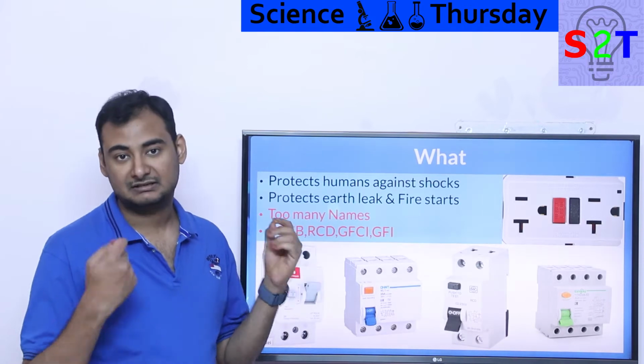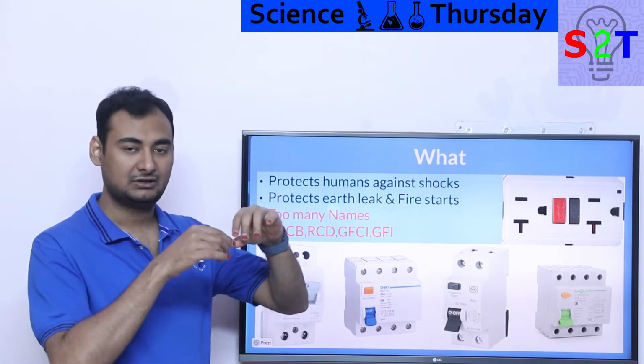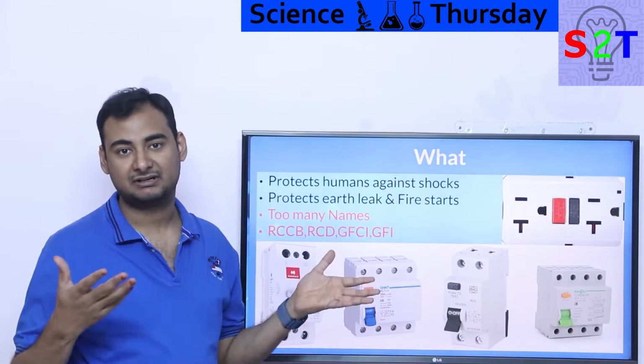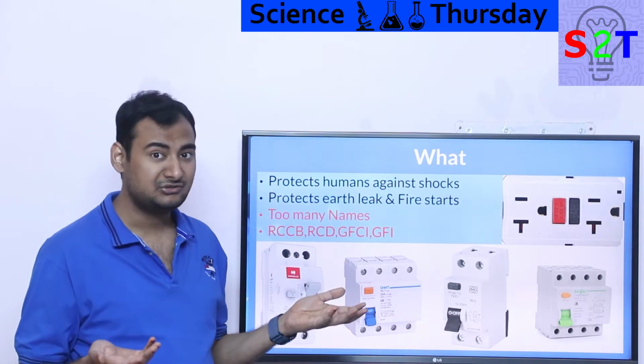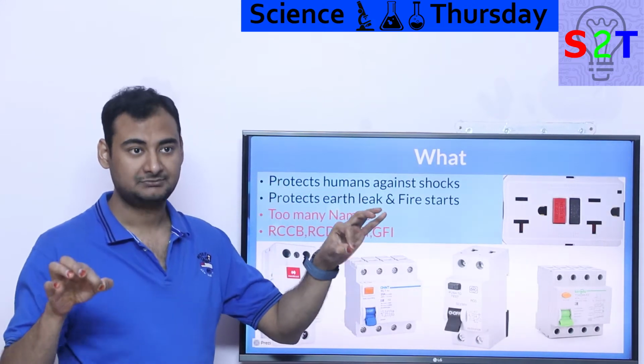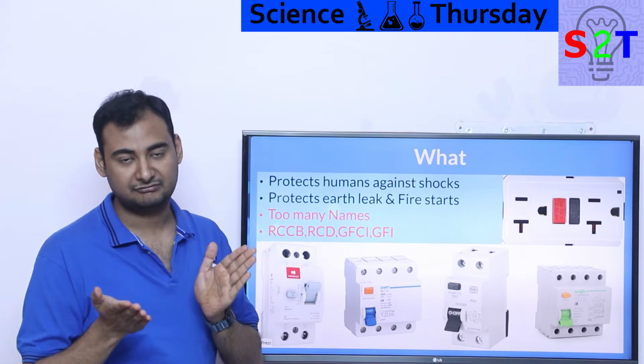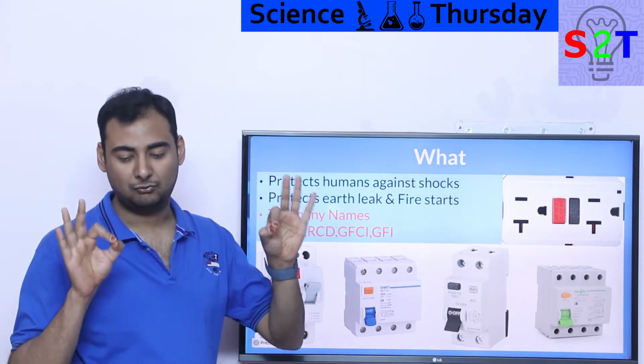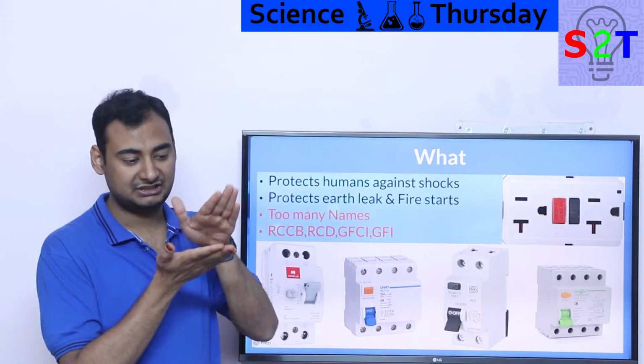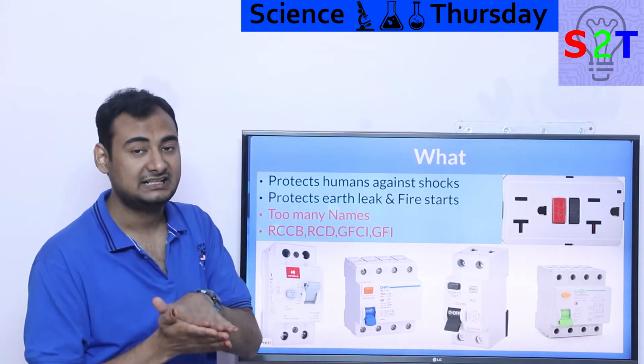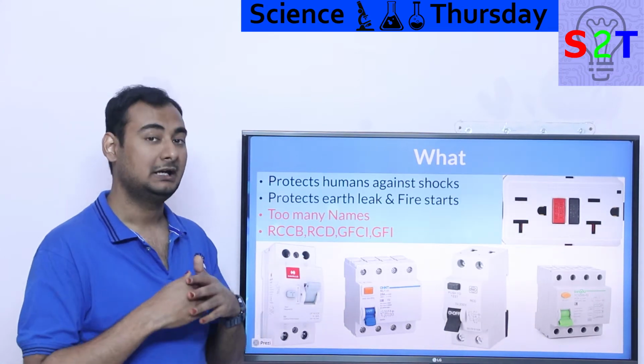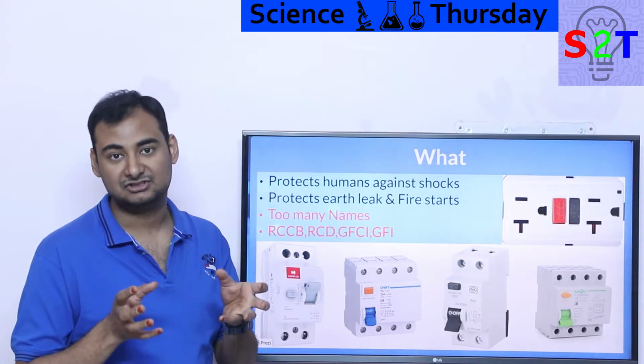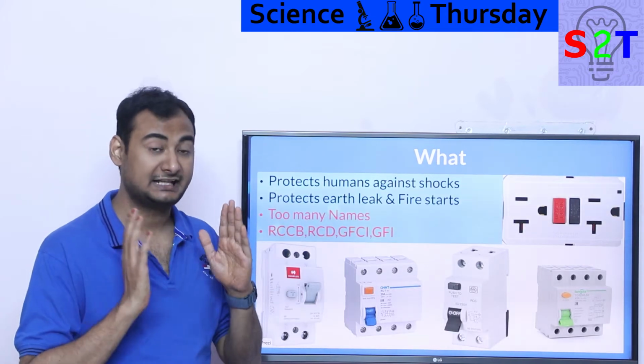Now, earth leakage can sometimes directly cause fire. Think of it this way: you have a wood. Now, wood behaves differently based on weather. Like let's say in a high humidity environment, if you have a raw conductor, let's say your insulation failed and you just have a normal wire, let's say a rat chewed it through, but it's now lying directly on the wood, it could set the wood on fire over time because of small current. First it will char it and then it will set it on fire, and that has happened.